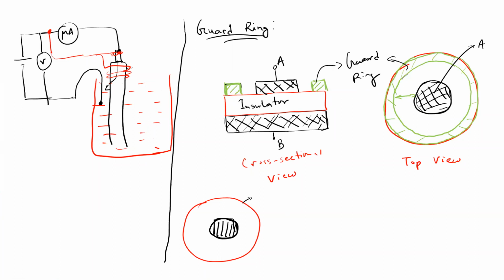The purpose of the guard ring is to bypass the leakage current. The current flowing through the surface of the insulating material, that leakage current, can be bypassed through the guard ring.